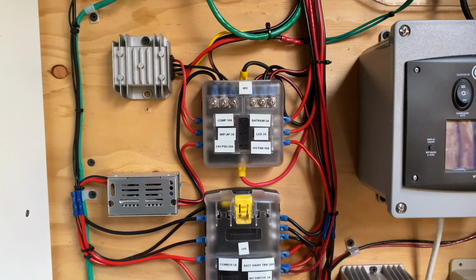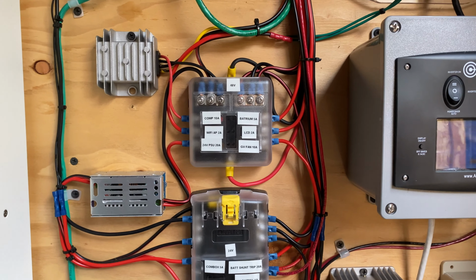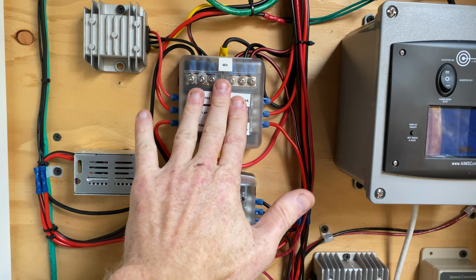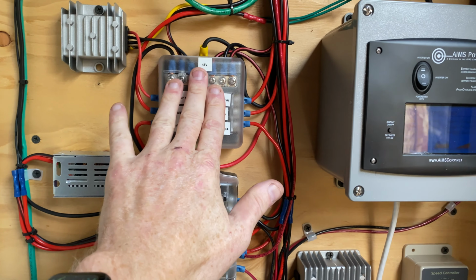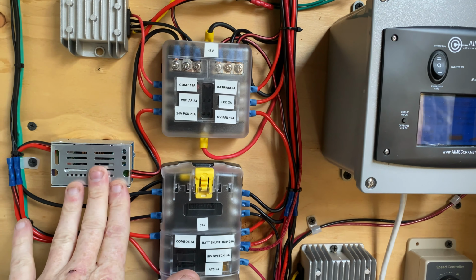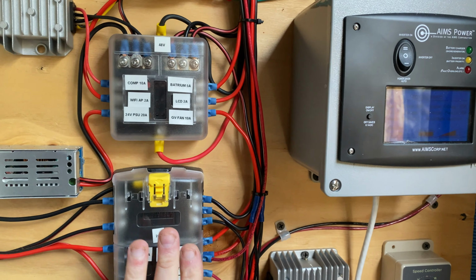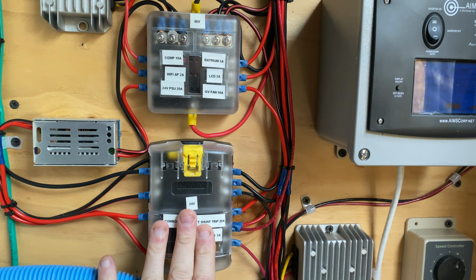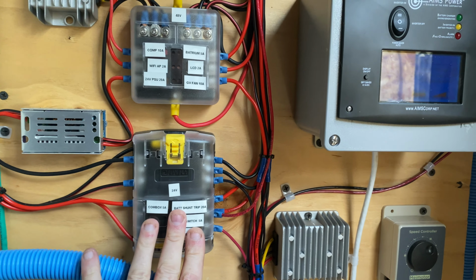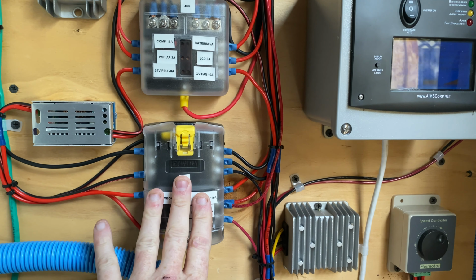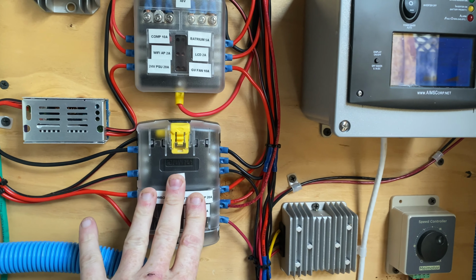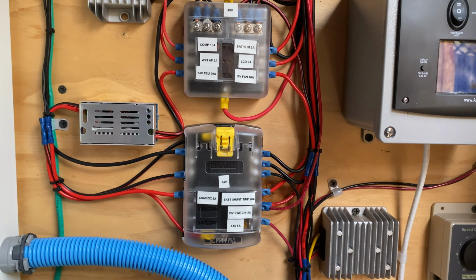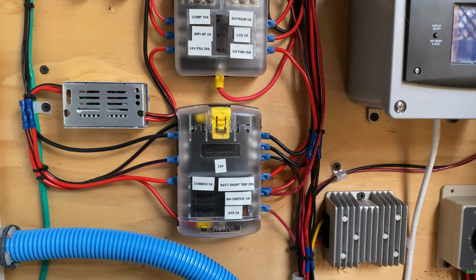Coming back to the wall, starting in the middle here, we've got a 48 volt block, which comes directly off the battery. Then we have a step down from 48 to 24 volts, which powers this block, used for all the 24 volt control systems. Several things rely on 24 volts, like my contactors, the ATS, and the shunt trip breaker for the whole system.